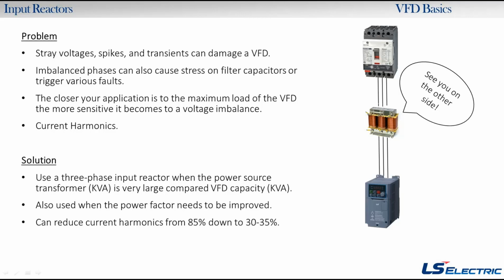What current harmonics are, in short, is that the input of the drive is a diode front end, okay, and that's going to pull current in a nonlinear fashion, and that could create distortion on the power supply. And again, the power company doesn't like it. They could bill you for that, or give you some fines depending on how bad the noise is. But if you put an input reactor on here, that's going to solve a lot of these problems we're listing up top. An input reactor will reduce the harmonics, looking at that bottom line. Without a line reactor, your harmonics could be as bad as 85%, but if you put our line reactor on there, you can get it down to about 30 to 35%.